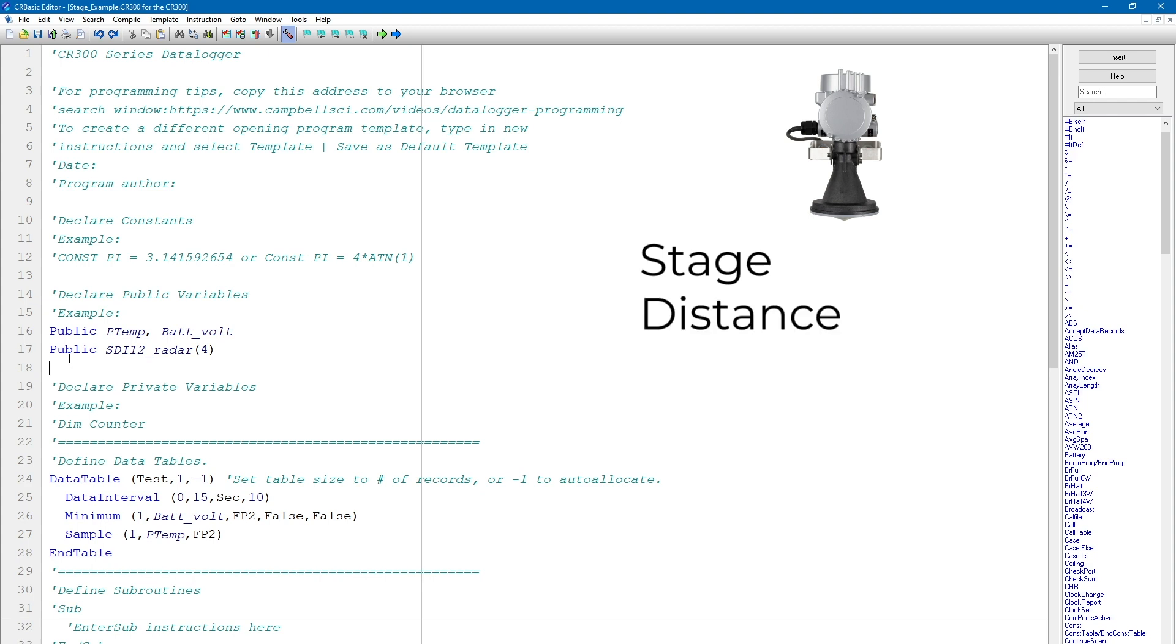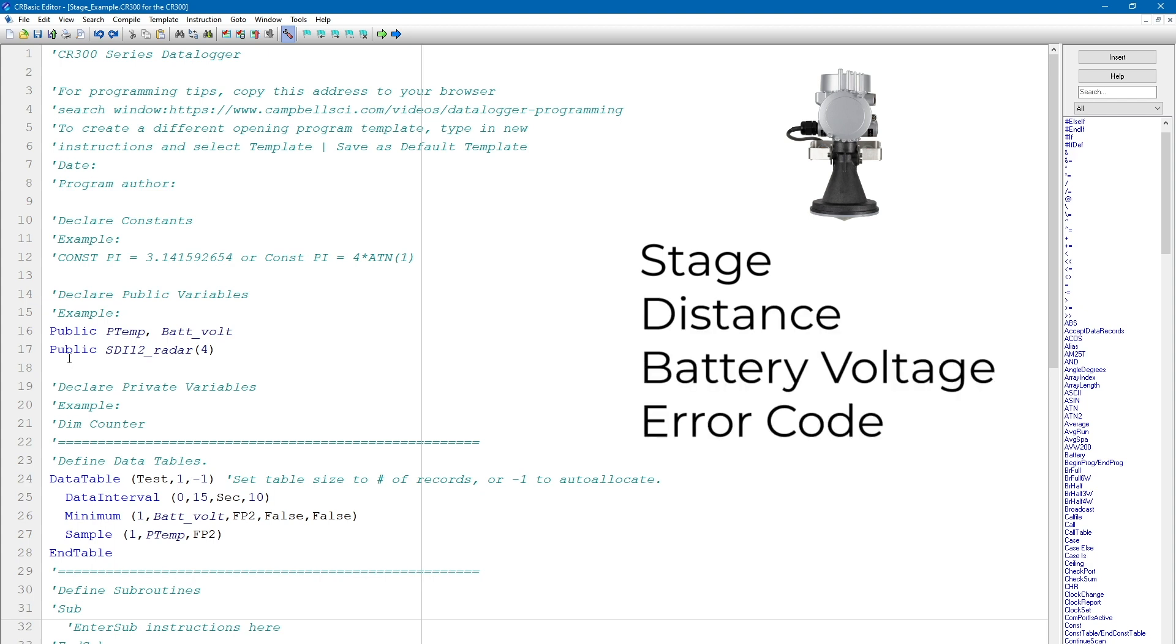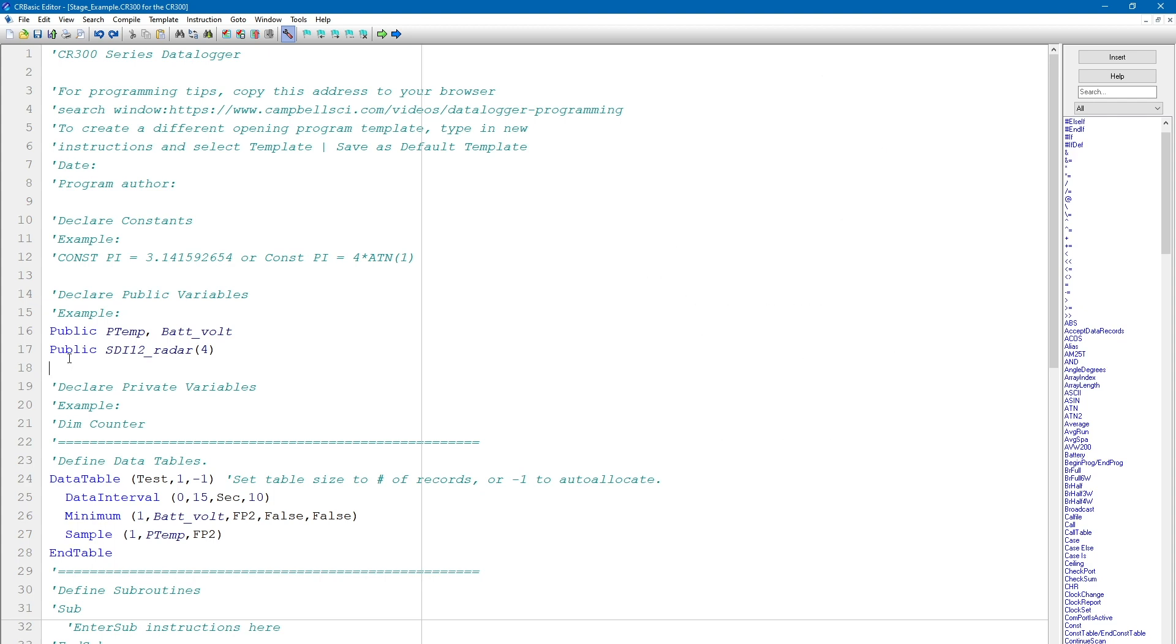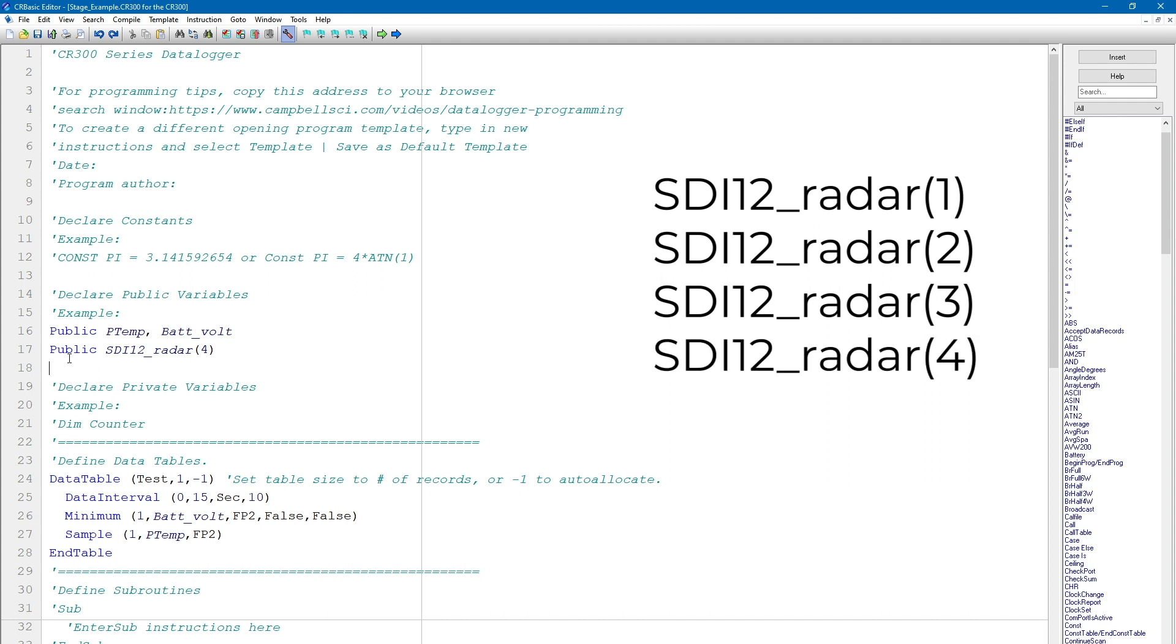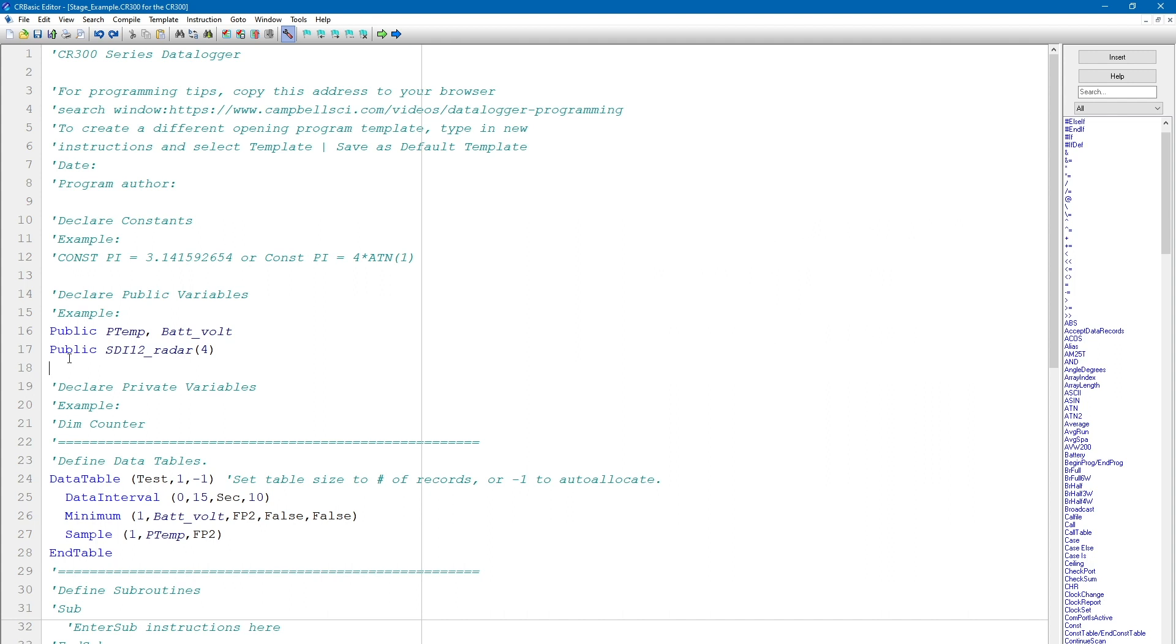Stage, distance, battery voltage, and an error code. Declaring the variable as an array of 4 creates 4 separate variables named SDI 12 Radar 1 to SDI 12 Radar 4, one variable for each value output by the sensor. I could use this array as is, but I'm likely to forget which output is stored in which variable. To make the outputs easy to identify, I will assign aliases to each of the 4 variables using the alias instruction.